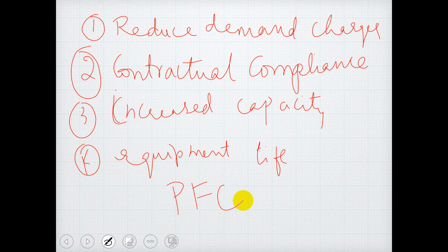We call that PFC. PFC is essentially a capacitor bank, which stores and provides reactive power when required. A poor power factor can also be corrected by fixing the problem at its source, for example by ensuring that motors are not oversized, and selecting pumping equipment with electronic variable speed devices. We call those VSDs, which means variable speed drives. Retrofitting VSDs where possible and choosing equipment that has good power factor to begin with. So these are the ways to improve the power factor.